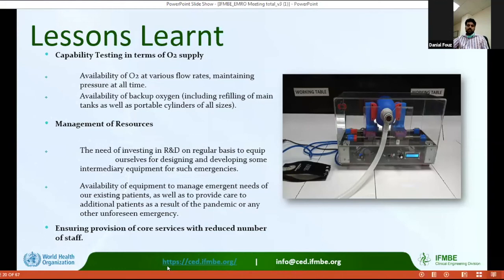Using easily available local parts, our design included a compressor run through a programmed driver. Atmospheric air is used by the ventilator and no external cylinder is attached. External oxygen can be delivered to the patient using flow meters to control the patient's oxygen saturation. The main control parameters are the volume, breaths per minute, and the inspiratory-expiratory ratio. The second lesson is that we were limited in other cancer treatment services because of the unavailability of equipment and its backup. And this is also one of our big lessons, to make backups of medical equipment available to handle a situation like this. With the reduced number of staff because of social distancing, and our staff was also COVID affected, another big lesson is to maintain core services.